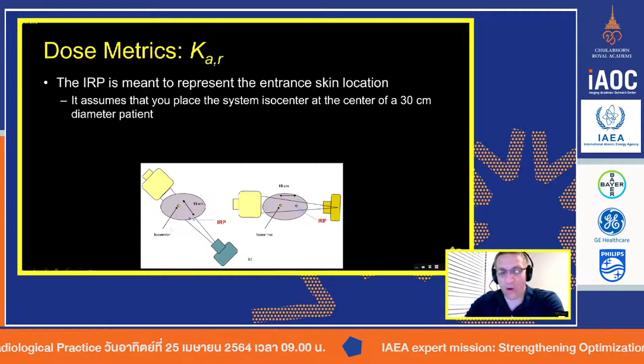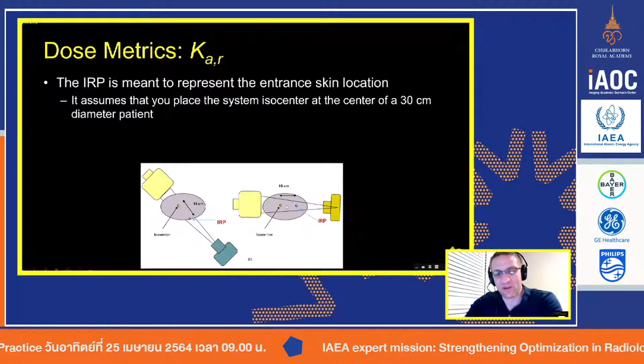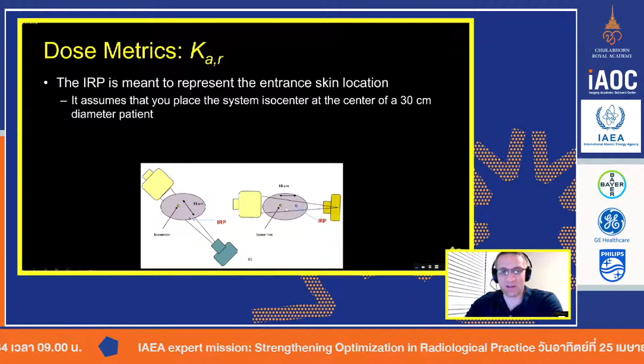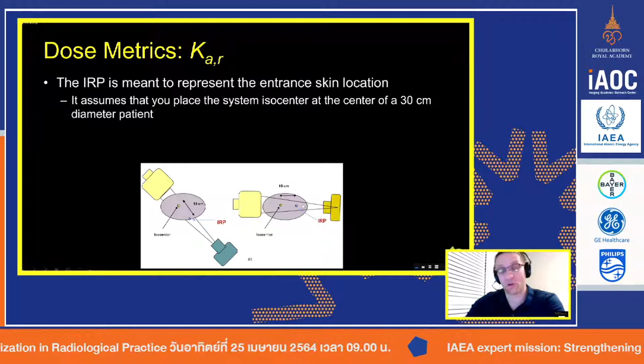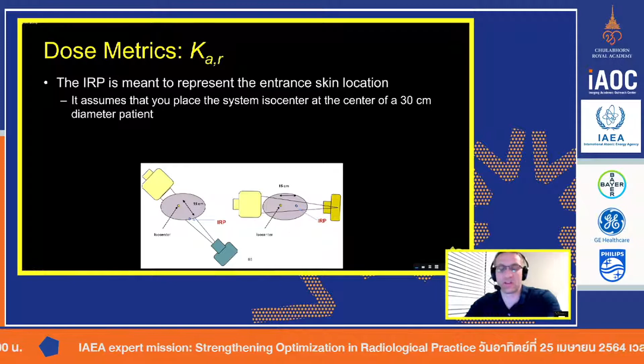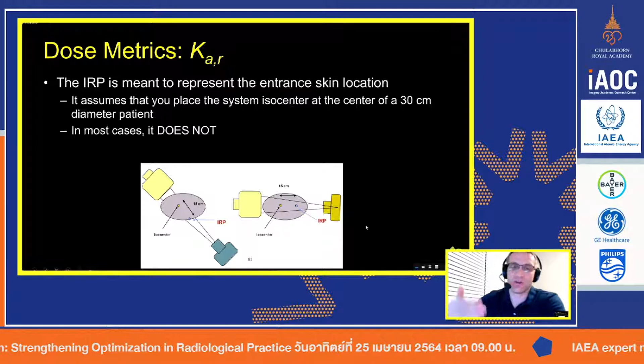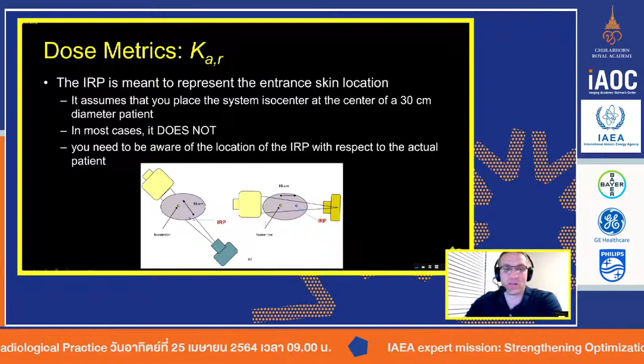So here you can see two geometries that aren't necessarily anterior posterior. You see here we're off on an oblique angle. In this case, the isocenter is off centered a little bit. It still works out that the international reference point is basically at the skin line. But in this case, now we've swung it all the way lateral. Isocenter is still in the patient, but now the international reference point is actually inside the patient. So the value that you would see on the screen is underrepresenting how much radiation dose you're getting to the skin. Now, if you're a teeny patient, which is more typical for pediatrics, that international reference point might be outside the body, might be lower, in which case the value you see on the screen is overrepresenting. So you have to know where the international reference point is when you go to do some calculations, if you need to know how much radiation dose the skin and the patient received.